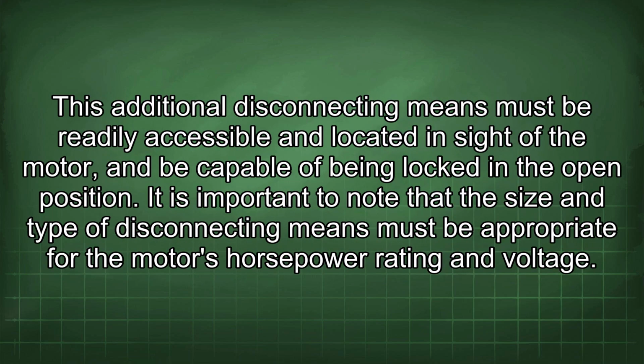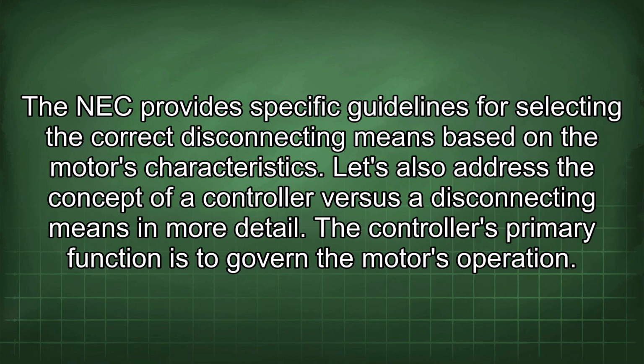This additional disconnecting means must be readily accessible and located in sight of the motor and be capable of being locked in the open position. It is important to note that the size and type of disconnecting means must be appropriate for the motor's horsepower rating and voltage. The NEC provides specific guidelines for selecting the correct disconnecting means based on the motor's characteristics.